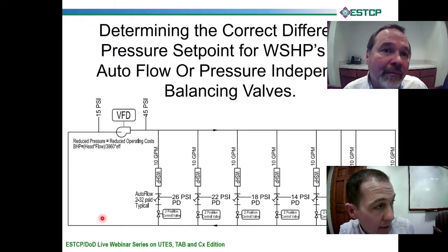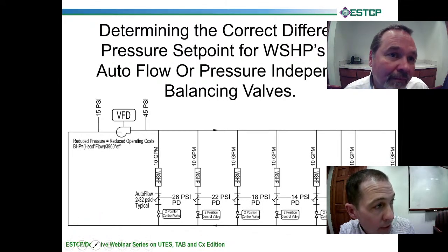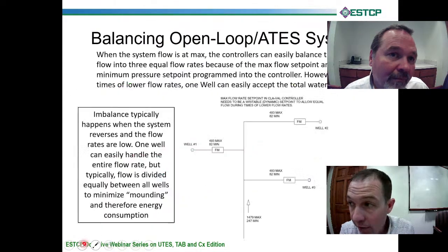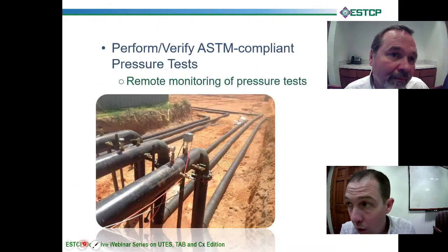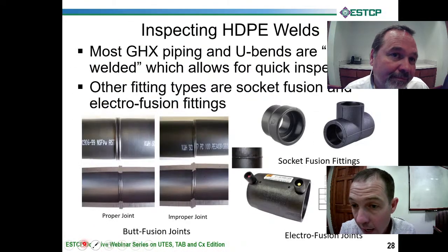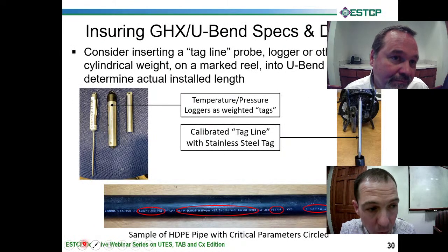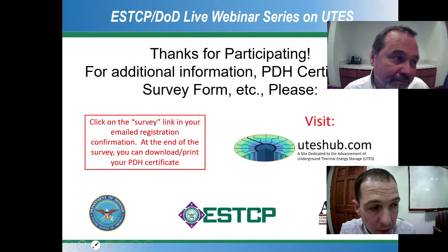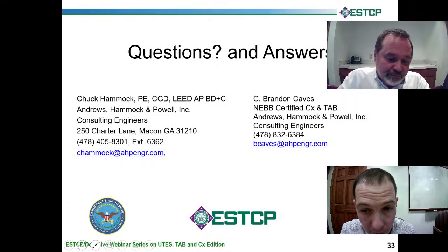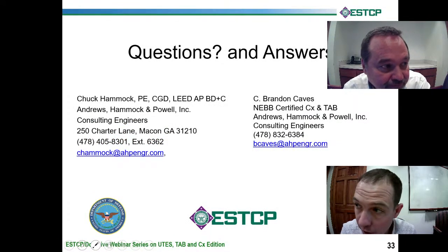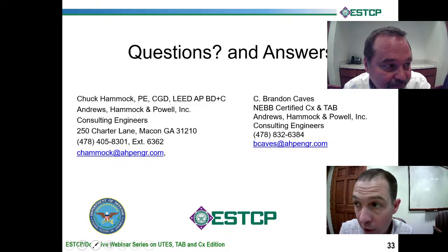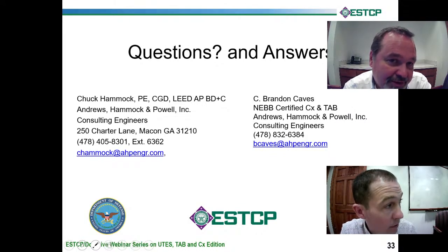Yes, I agree. The problem with automatic flow control valves is that the control system doesn't know whether they're fully open or fully closed. So I will say that dynamic reset doesn't work very well with automatic flow control valves. I said that a little bit wrong. With the two-position control valves, right? They're not modulating. Whereas on the modulating control valves, the control system has something to look at to see which ones are open, which ones are closed, or which ones are in between. Yeah. So get more specific with that.